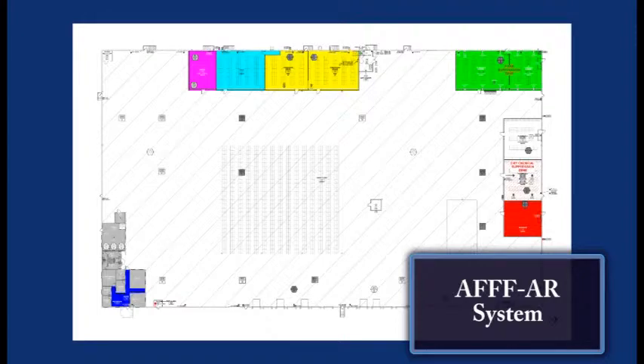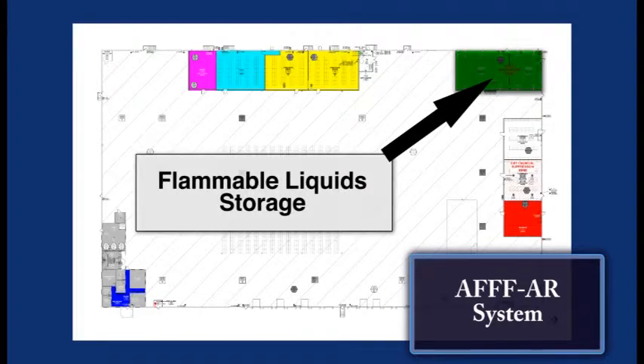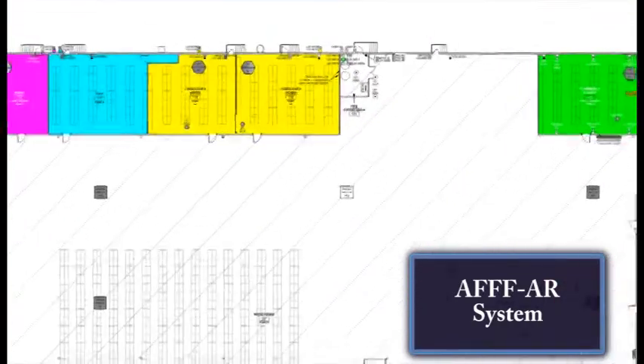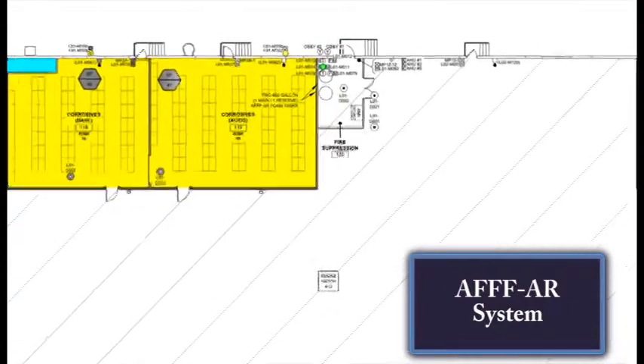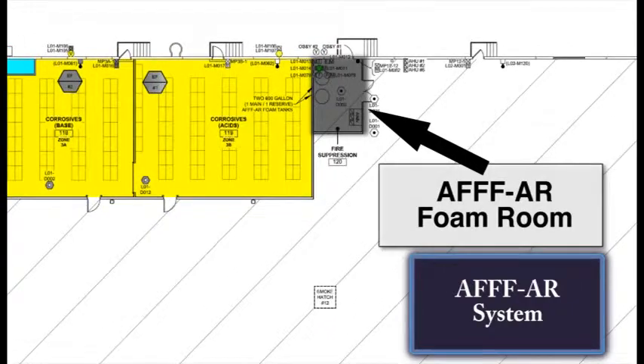An aqueous film-forming foam, alcohol-resistant, or AFFF-AR system provides coverage for the flammable liquid storage area. The AFFF-AR tank, foam water proportioner, and associated valves are located in a dedicated AFFF-AR foam room adjacent to the corrosive acids room and central to the location of the flammable liquid storage area. This facilitates shorter foam extinguishing agent release times once a system is activated.